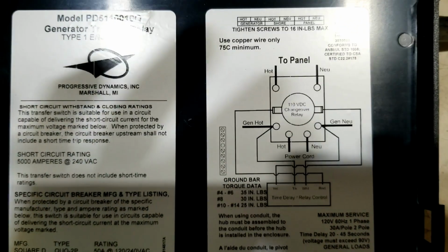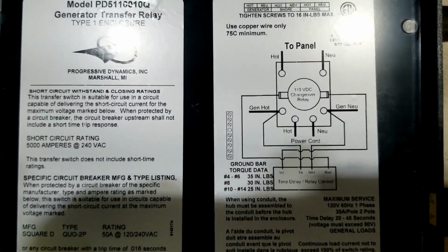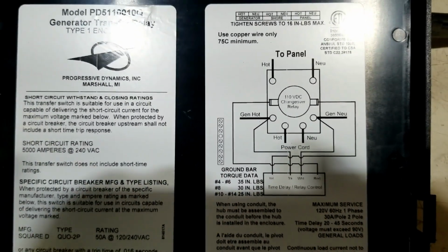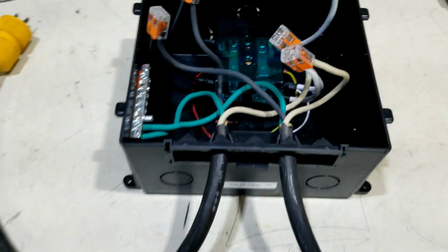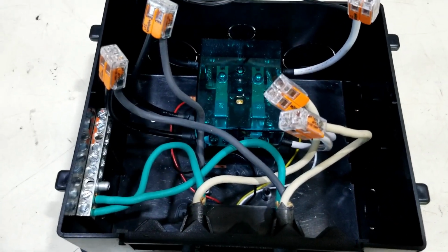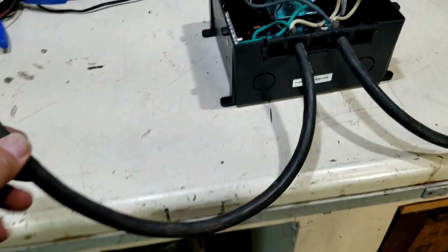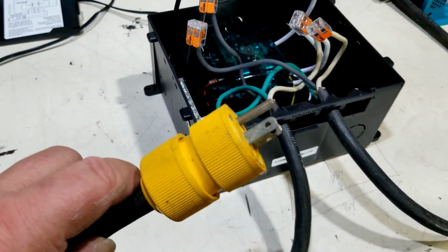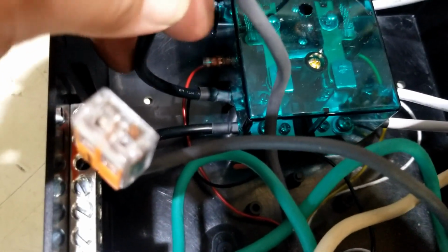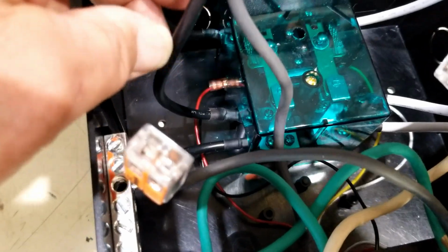Since I'll be connecting this to an inverter and not a generator, I'm going to hook it up a little bit differently, and I'll show you why. What I've done to demonstrate how this automatic transfer switch works is I've connected two power plugs. You can see one there. The one that has the yellow connector actually goes through, it's this wire right here, and you can see it's connected to the terminals that on their instructions say would go or come from generator power.